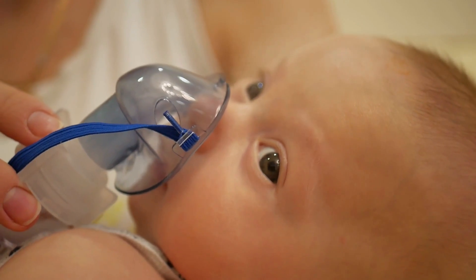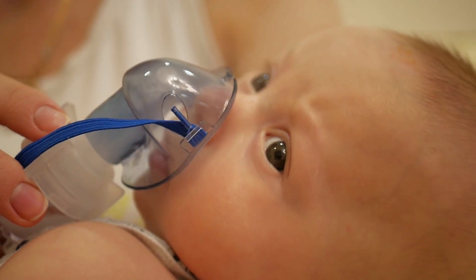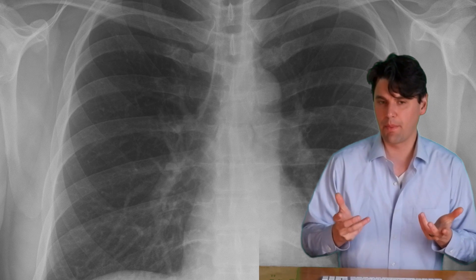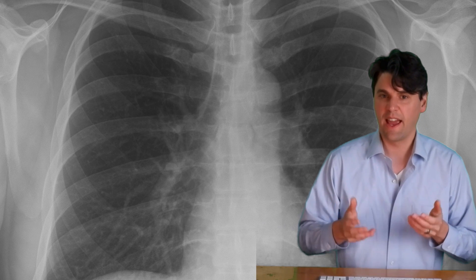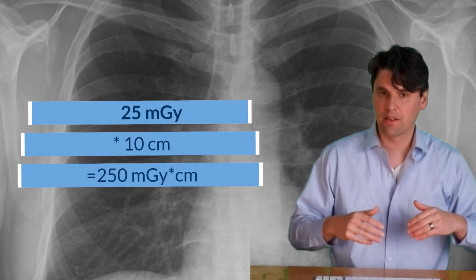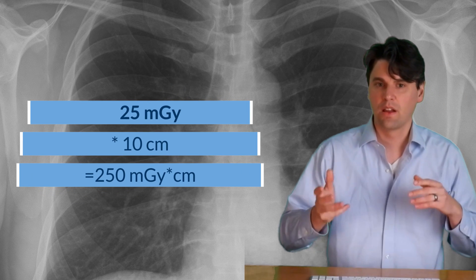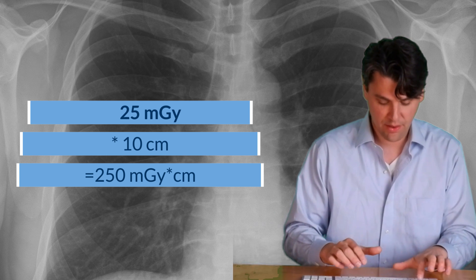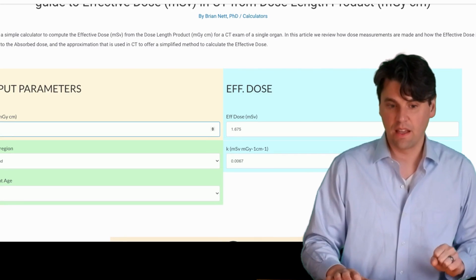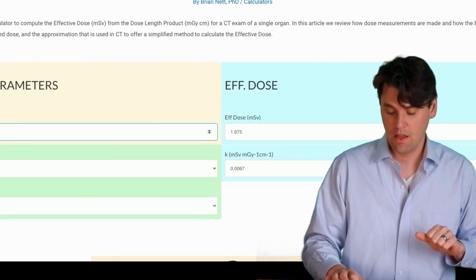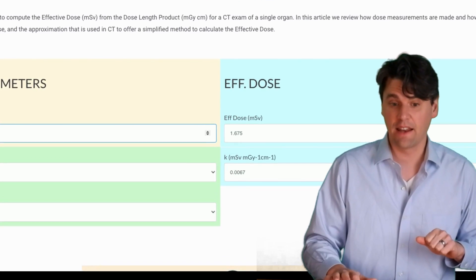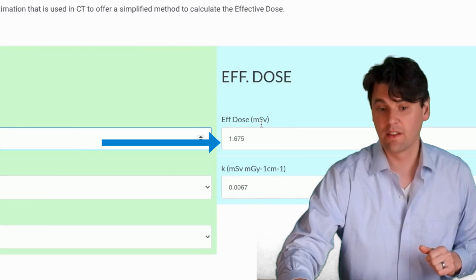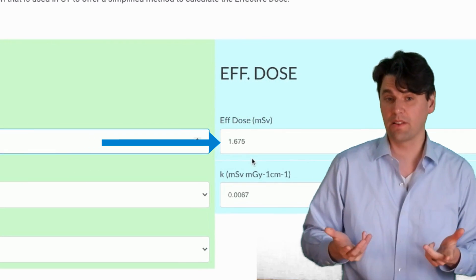If a one-year-old comes in for a CT scan, the radiation dose that would be used would typically be lower — maybe 25 milligray would be representative — and the distance that would be scanned would be less, so maybe 10 centimeters. So if we say 250 milligray centimeters is what the scanner would output, you can see if we select a one-year-old and a head, the effective dose is still below two millisieverts.